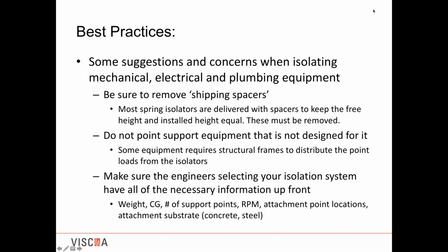The pad has no effect on the isolation system. It's more of a means of housekeeping. It's a means of raising the equipment off of the floor slightly in case there's any water intrusion in the building, or to keep debris from going underneath, but it has no impact on the vibration isolation system. It may have an impact on the seismic, but right now that's beyond the scope of here.